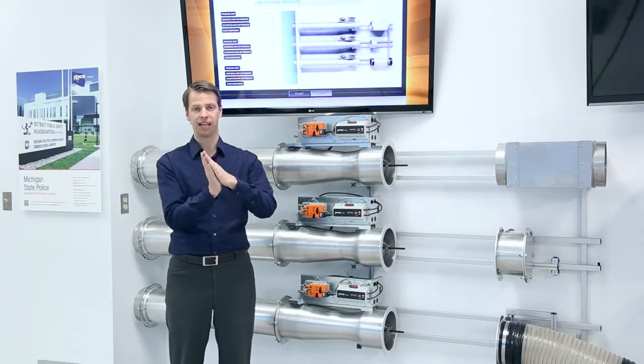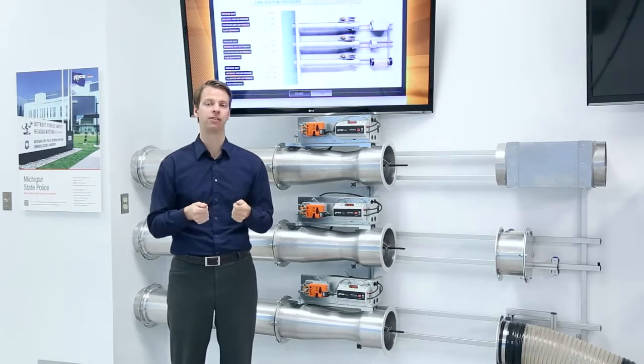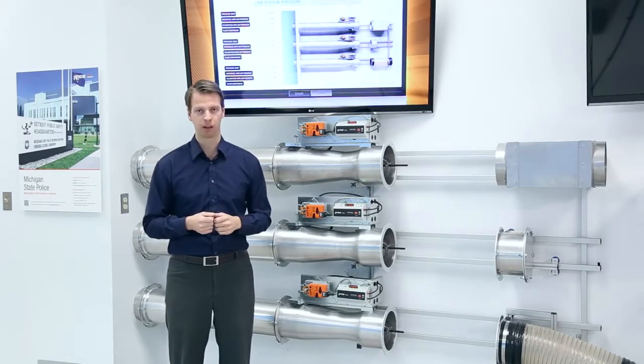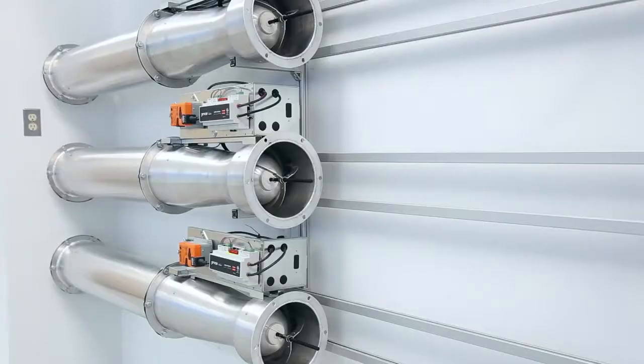Essentially you need to drive that damper open and closed to maintain your airflow as you have any changes in system static pressure. Now a Price-Venturi valve doesn't operate like that. It has an internal mechanical cone spring assembly which automatically adjusts for changes in your system static pressure.